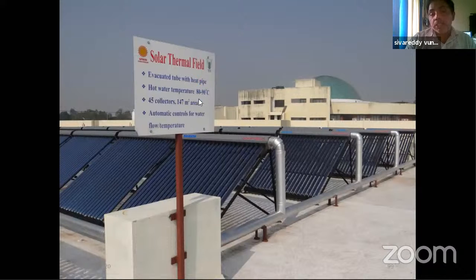The hot water temperature of 80 to 90 degrees is designed, but luckily we easily got 90 to 95 degrees. Why? Because in our solar radiation estimation we assumed 600 watt per meter square on average, but where we installed it, at Anand Agriculture University, the solar radiation is more than 600. Why? Because an agriculture area means a less polluted area. While solar radiation is coming, if more pollution is there, absorption of the radiation will take place. With less pollution, we achieve more solar radiation, and that's why we are achieving higher temperatures.